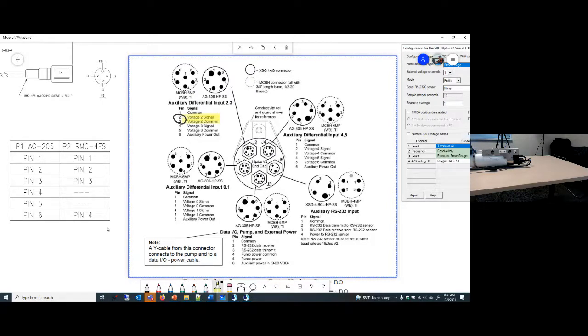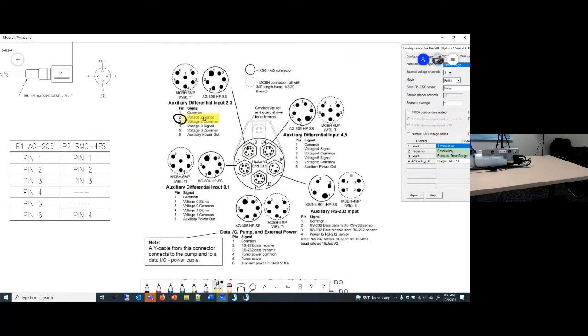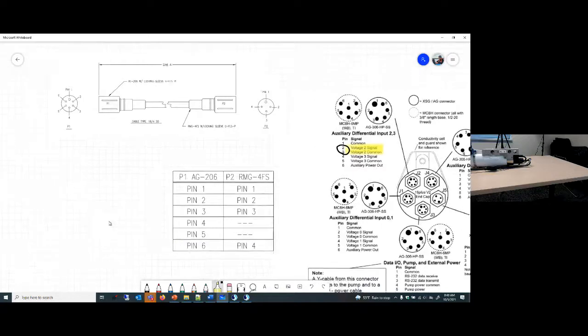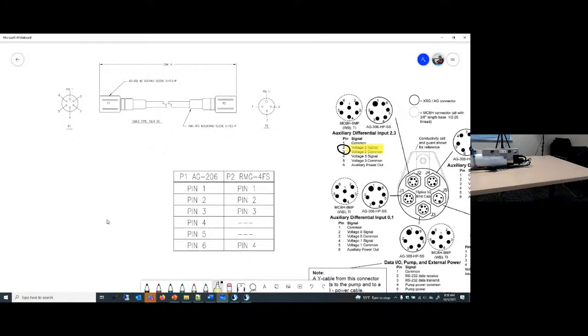So what that means is our oxygen sensor is either putting data onto voltage 2 or voltage 3. Now, in order to identify which channel it's putting the data onto, we need to look at the cable we're using to connect our sensor to our CTD.